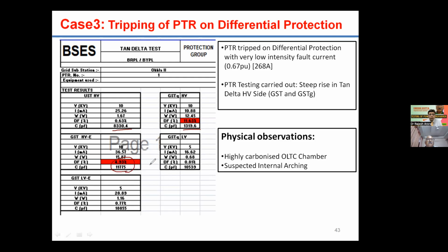So we planned for inspecting the transformer through the inspection plates, and what was found was that the OLTC barrier plate was highly carbonized. The chamber was completely carbonized because of some internal arcing, due to which the insulation level of this transformer suddenly started to decrease. So thereafter, the corrective action was taken. The chamber was cleaned, and the connection tightening was carried out at the barrier plates, and it was re-energized.